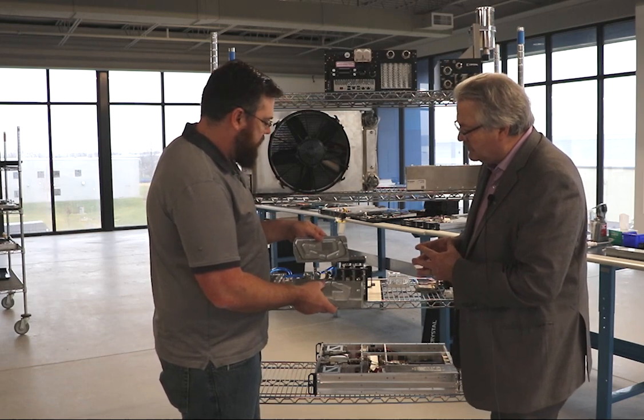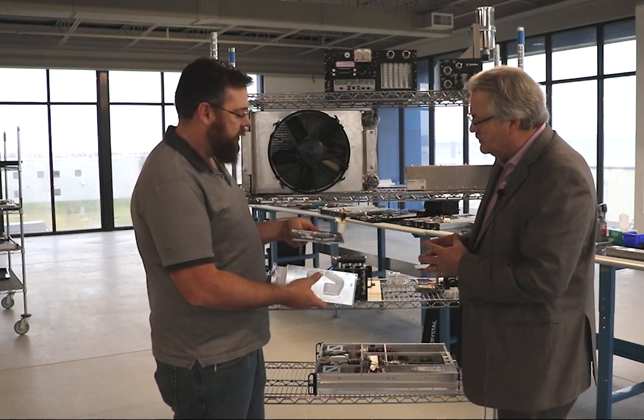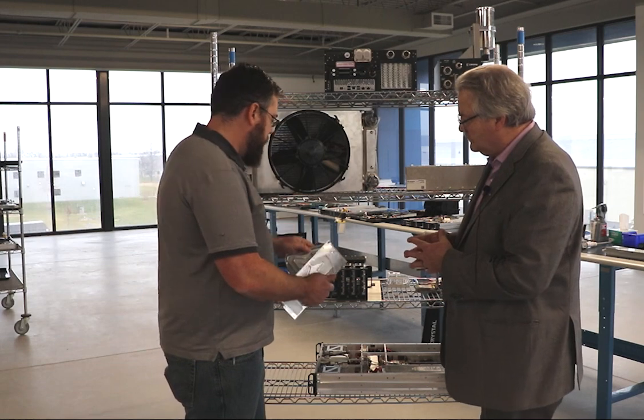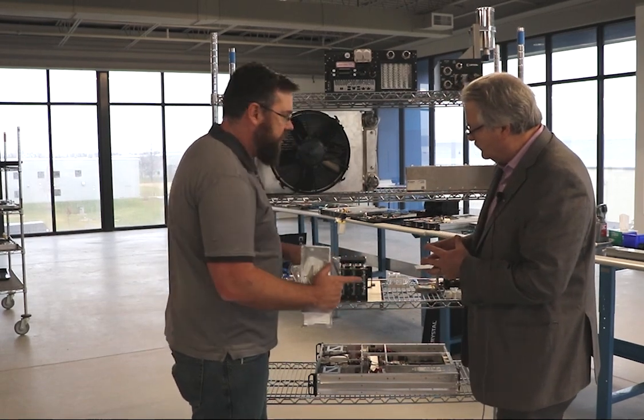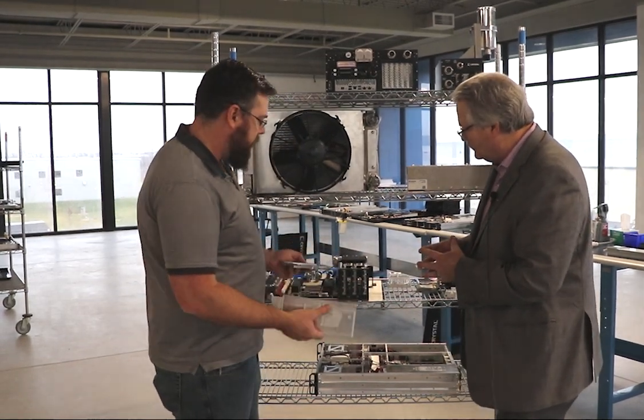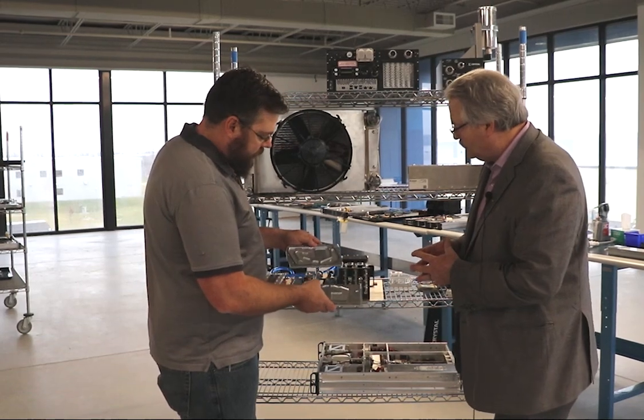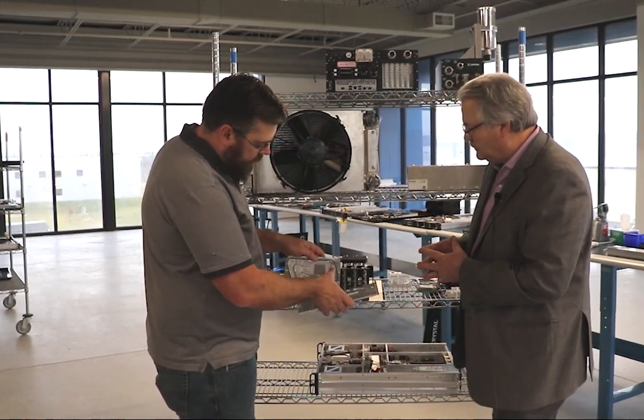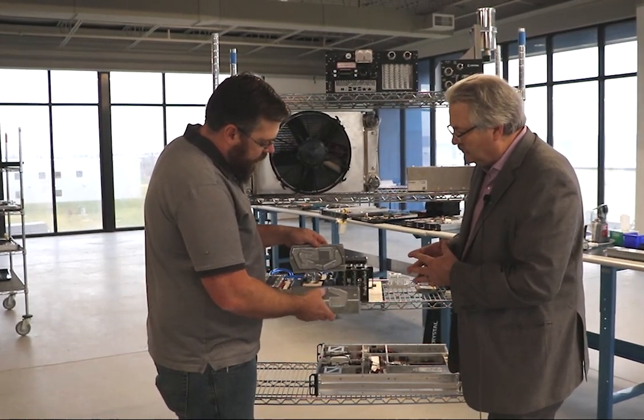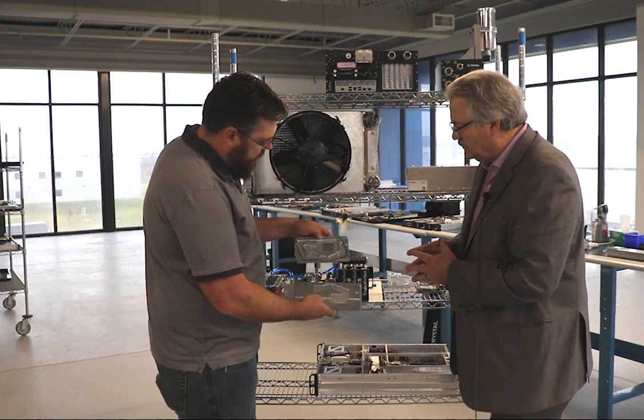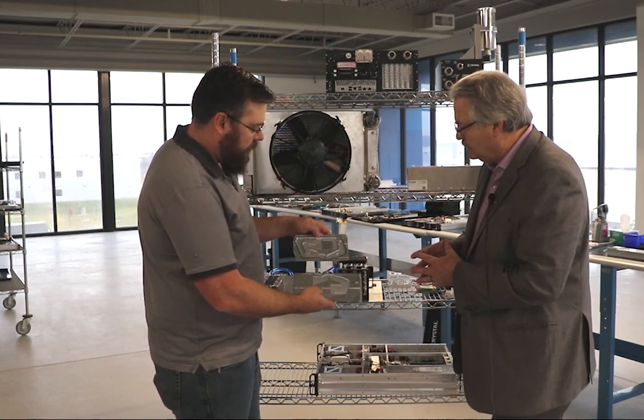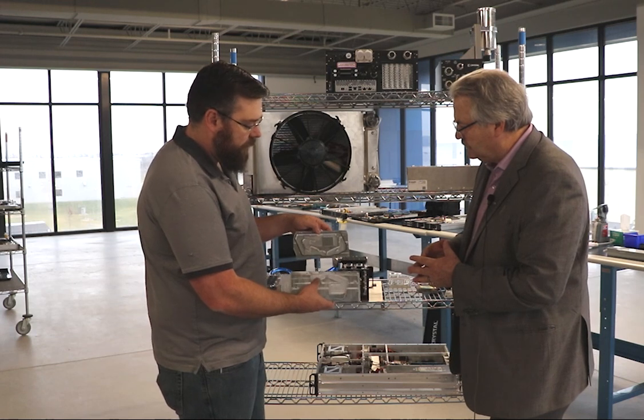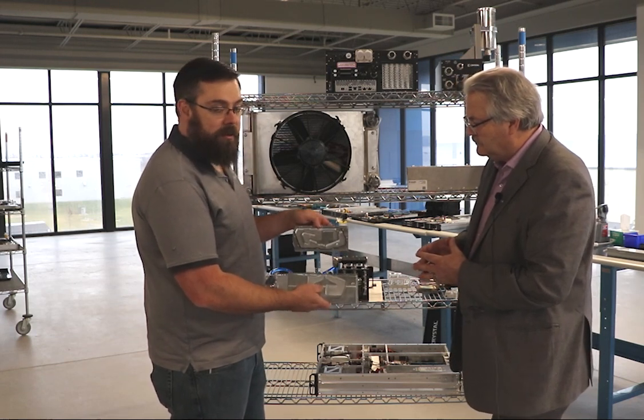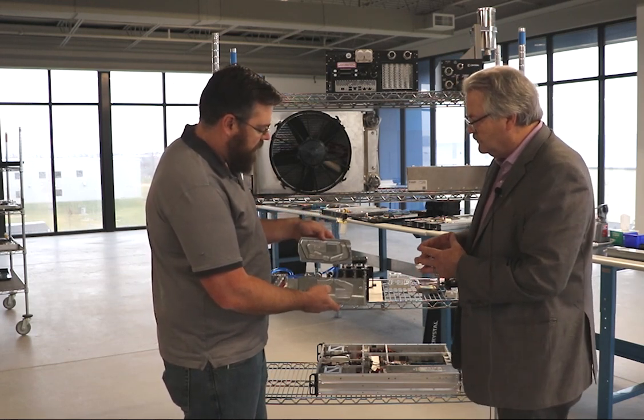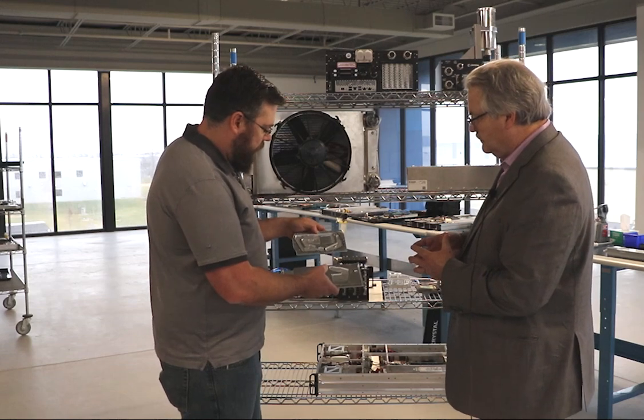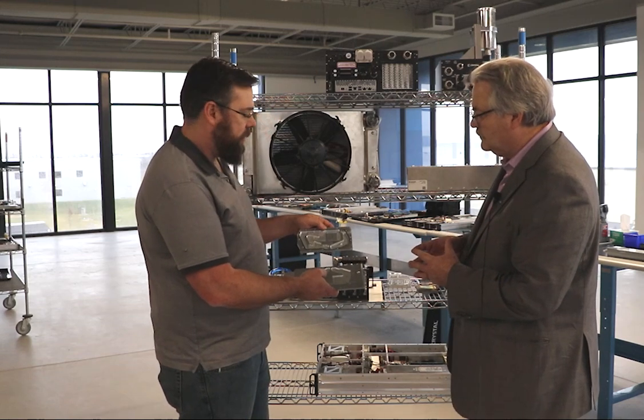Space is always a huge consideration in these designs. We're often trying to fit cards into a smaller area than they'd occupy when air cooled. That leads us to create channels and different geometry that could cause pressure drops and situations where we wouldn't get proper flow through the heat sink. So we run a lot of different simulations and techniques to generate lower pressure drops.